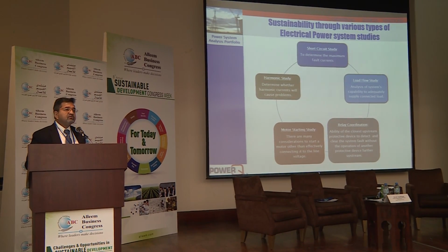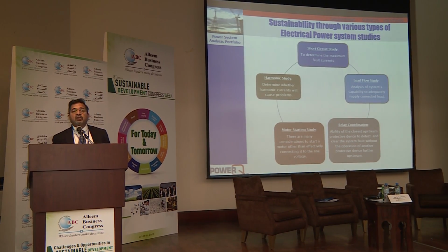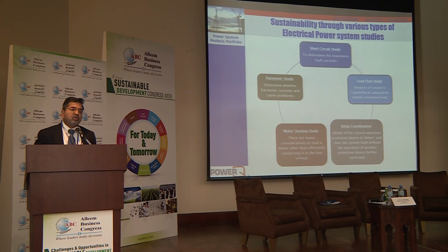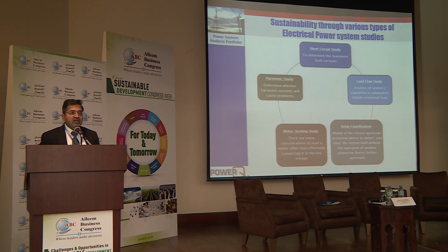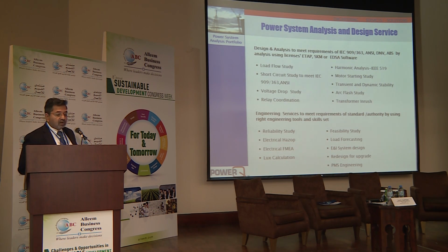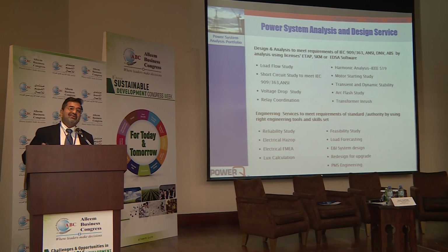Now these 3 studies, the short circuit study, the relay coordination study, and the load flow study, are the basic studies which are used for most networks, either in the beginning of a project, or in between when customers have organically grown their loads and their generation and they need to have a relook at their systems. Besides, we also have other additional studies like the motor starting study and the harmonic study. Now, of course, these studies are all conducted under the realm of standards.